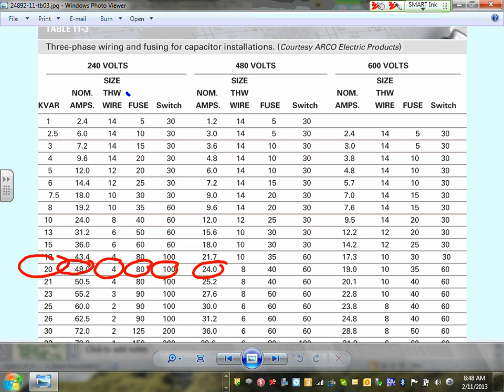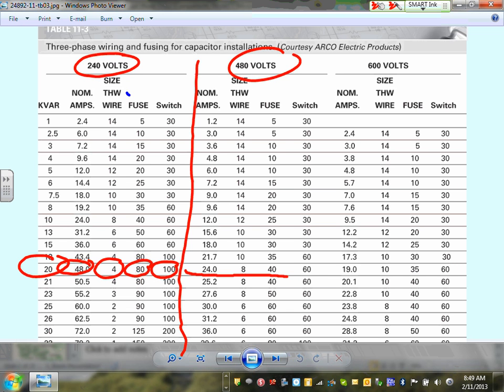And here's your nominal amps for this baby. No, this is not the second size. Nominal amps. Okay, so the 480. So that's basically, if your voltage is running at 240, you have to cut it right in here. There you go. Does that make sense, guys? So if my system is 480 like ours, then here's all the information that you need to size. So let me ask you, Brian, my friend, if I have a 20 kVAR capacitor, the full load is 24, the conductor size is number 8, the fuse is 40, and the disconnect is 60. Already sized for you, no question asked.